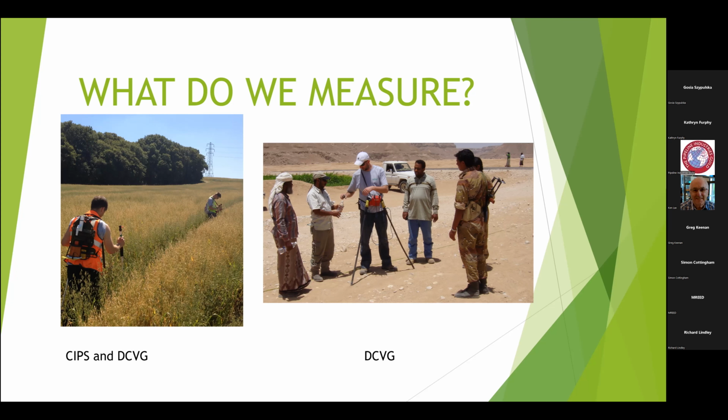If you look at a stream running down a slightly sloped pasture, that's not such a steep gradient. Well, if you could see the lines of equipotential in the ground coming from the anodes or the interference, it would look like that, like either a waterfall where you get a steep gradient or a gentle slope. And with those 2 sticks, he's able to detect that.